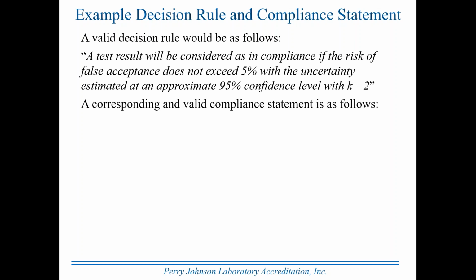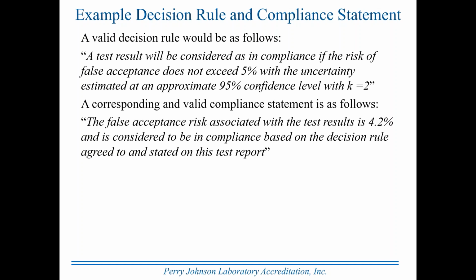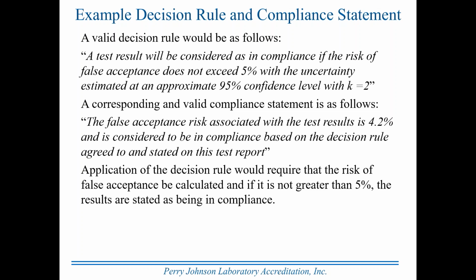A corresponding and valid compliance statement is as follows. The false acceptance risk associated with the test results is 4.2% and is considered to be in compliance based on the decision rule agreed to and stated on this test report. Now, it could be a calibration certificate just as easily. Application of the decision rule would require that the risk of false acceptance be calculated, and if it is not greater than 5%, the results are stated as being in compliance. So you have a decision rule, you have a compliance statement.